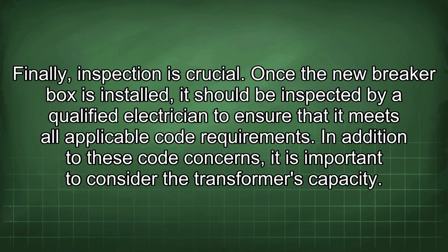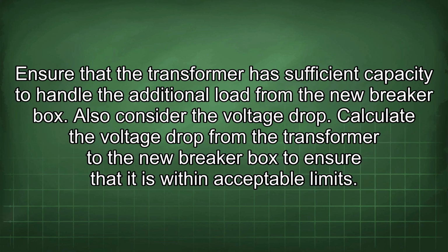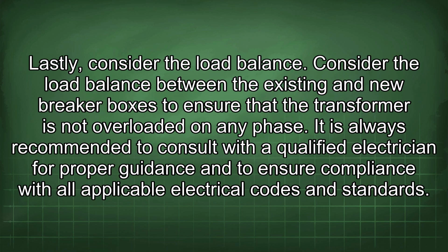In addition to these code concerns, it is important to consider the transformer's capacity. Ensure that the transformer has sufficient capacity to handle the additional load from the new breaker box. Also consider the voltage drop. Calculate the voltage drop from the transformer to the new breaker box to ensure that it is within acceptable limits. Lastly, consider the load balance.